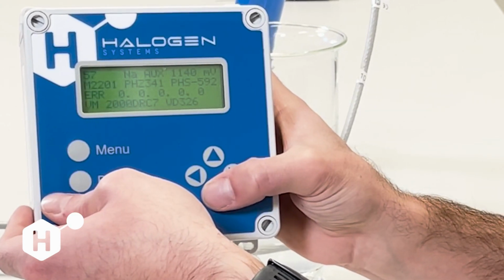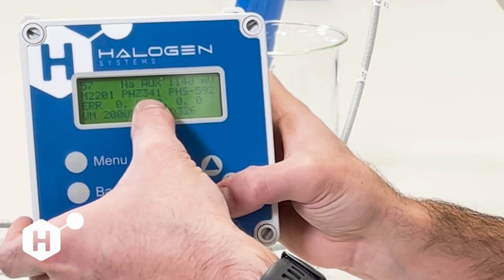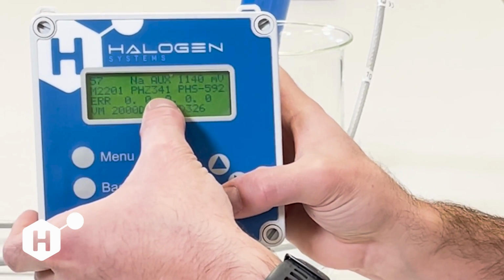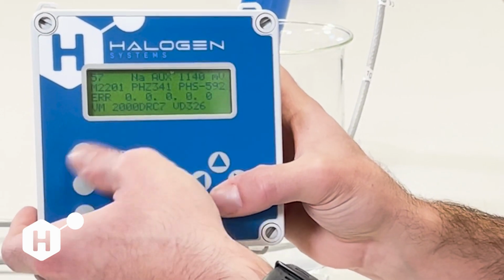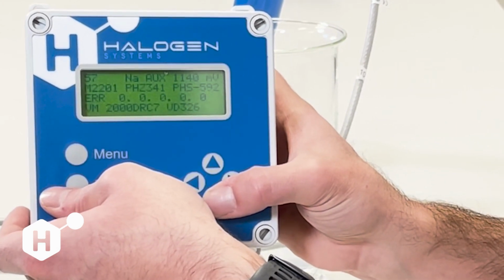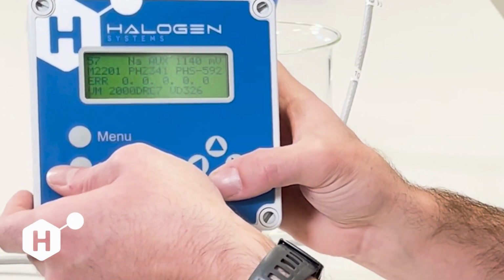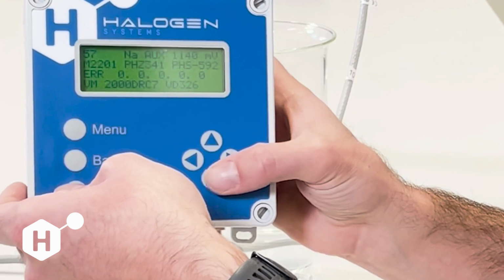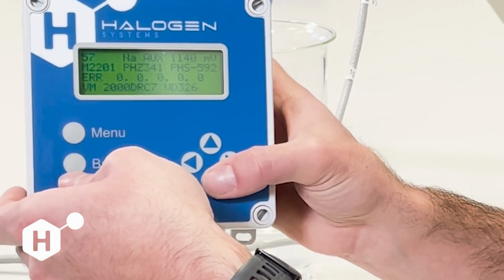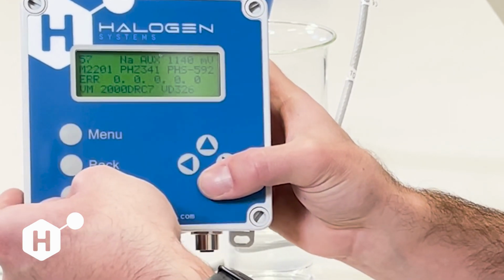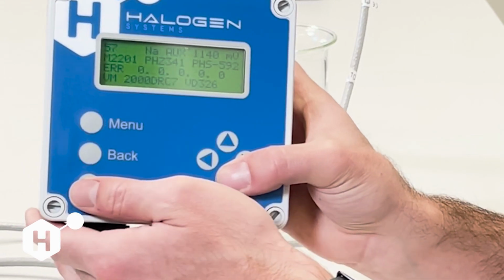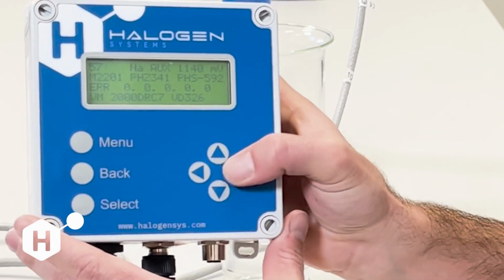The other place that we can confirm that our pH 0 has changed is by looking at the pH Z here, and it's 34.1. What that's telling us is that we did our 7 buffer calibration when our pH sensor was reading negative 34.1 millivolts. It's just a simple offset where it's going to add 34.1 millivolts to align our pH offset calibration.